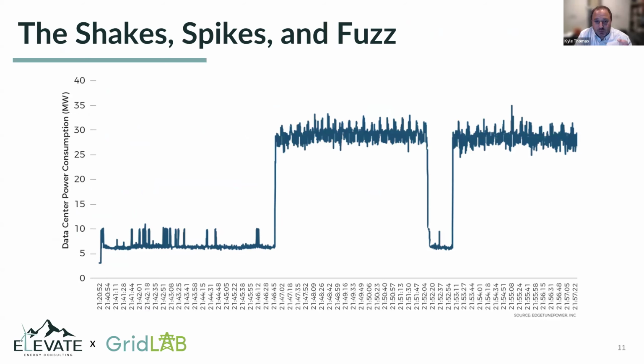A couple examples of some real data curves from some data centers show this cycling and these power quality problems. This is only a sample of a few minutes, but you're seeing huge variations in load - and I say huge, but this is one data center. These are 5-10 megawatts going up and down at very high speeds. You're talking about milliseconds to seconds of ramping in these fuzzy curves, unheard of typically before, maybe with the exception of an arc furnace.